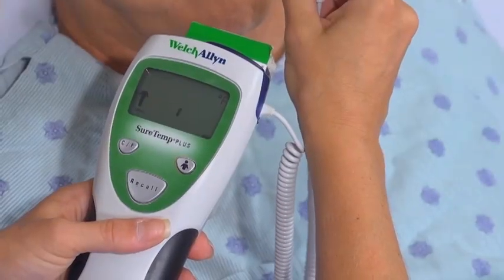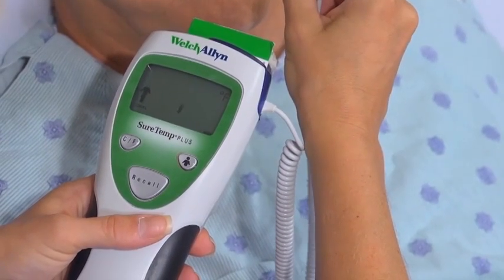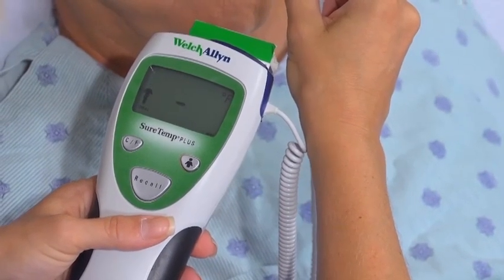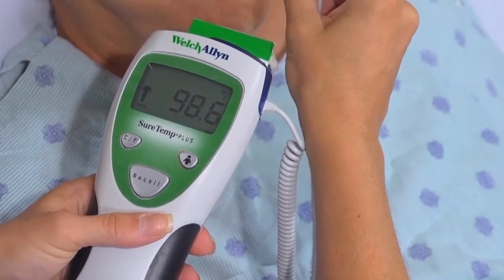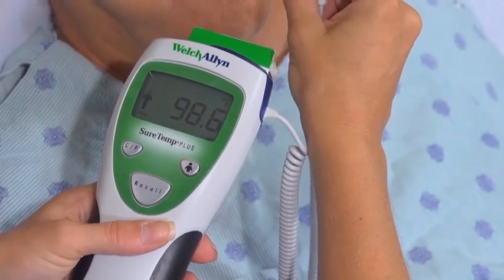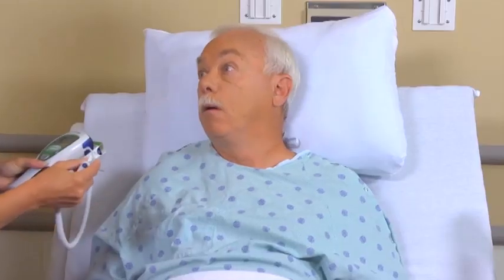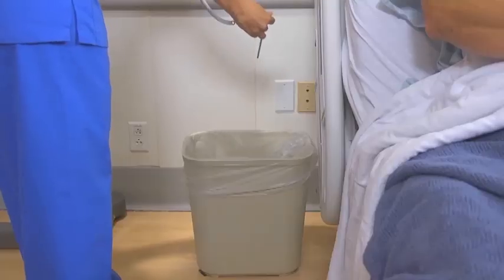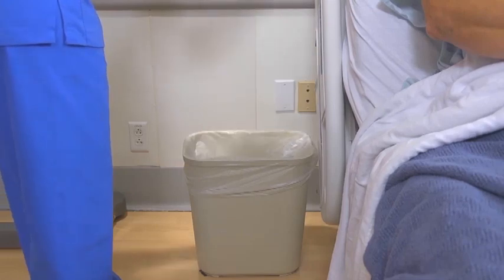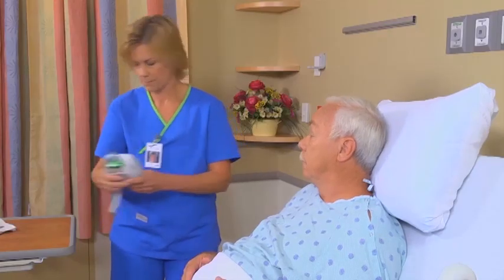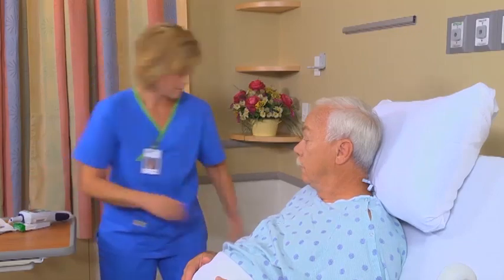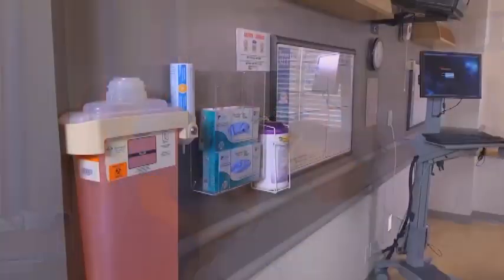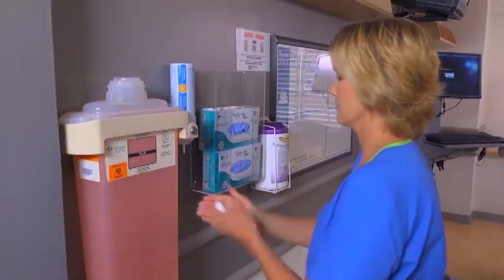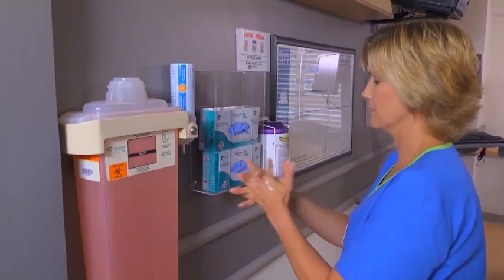Keep the probe in place until you hear the audible signal and the temperature measurement appears on the digital display. Remove the probe, read the display, and tell the patient his temperature. 98.6 is your temperature. Now push the ejection button on the probe to discard the cover in the trash. Return the thermometer probe to its storage unit. Remove your gloves if worn and perform hand hygiene.